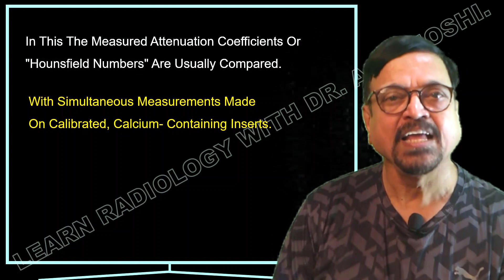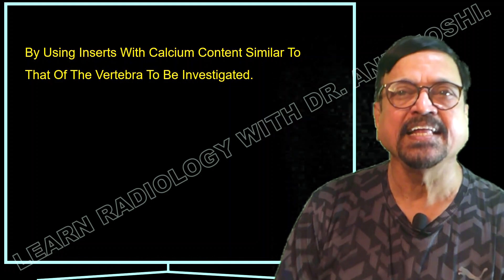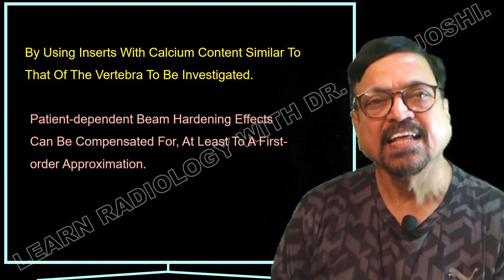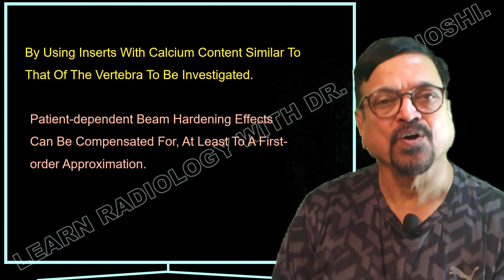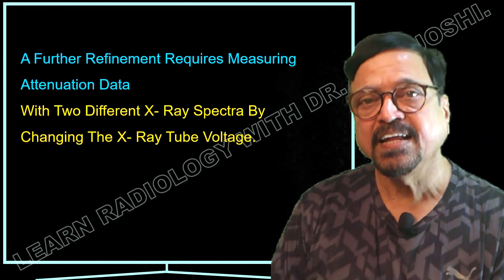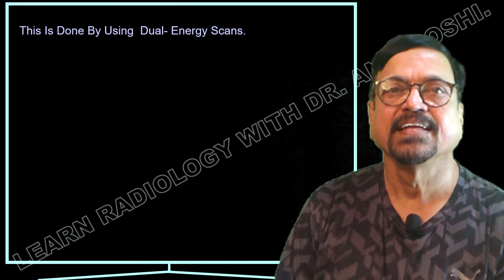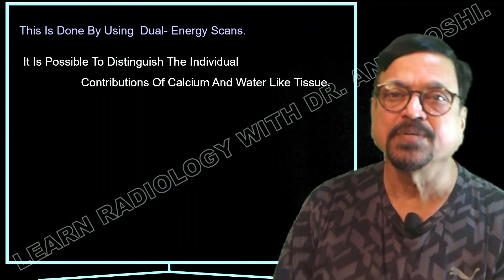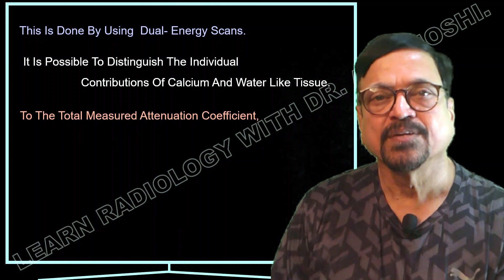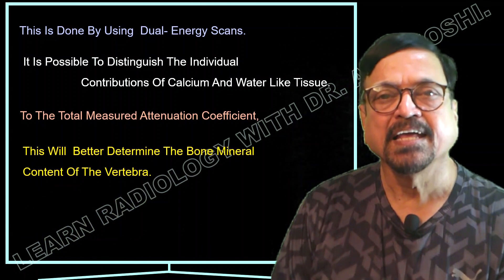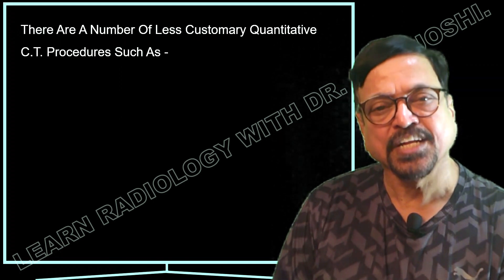This comparison is made with simultaneous measurement on calibrated calcium-containing inserts. By using inserts with calcium content similar to that of the vertebra being investigated, patient-dependent beam hardening effects can be compensated for, at least to a first-order approximation. A further refinement requires measuring attenuation data with two different X-ray spectra by changing the X-ray tube voltage — this is done using dual energy scans. It is then possible to distinguish the individual contributions of calcium and water-like tissues to the total measured attenuation coefficient, which better determines the bone mineral content of the vertebra.